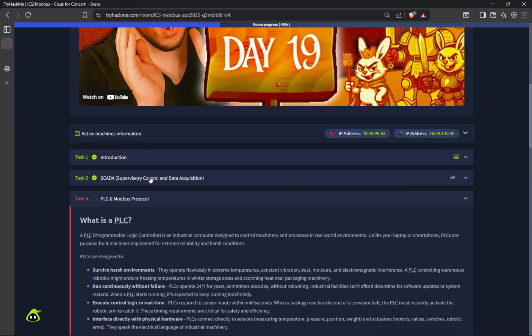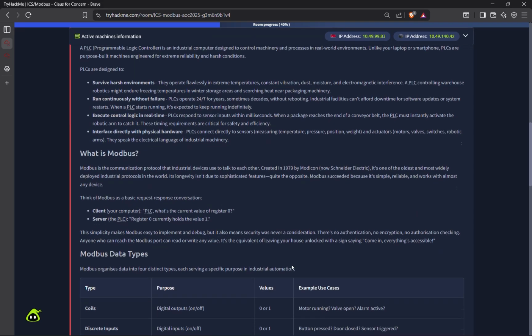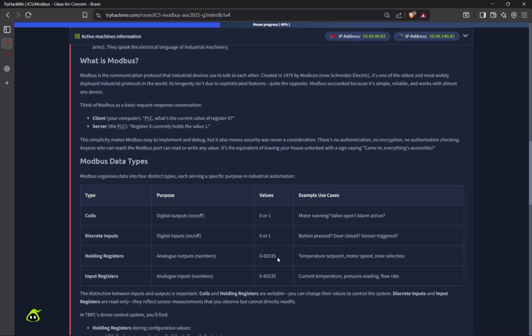Anyone who can reach port 502 can read or write values. That's why earlier they asked about Modbus data types. For example, a coil, which is 0 or 1, basically stands for whether the motor is running on or off.